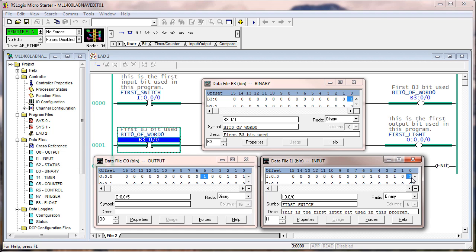If you have any bits on that are not in the logic, it's because I had you toggle them on and never had you toggle them off. This is an important characteristic of the controller's data table. If your logic turns on a bit and no one turns it off, it will stay on forever. You can double click on the output file and change any of those bits that are 1 to a 0.